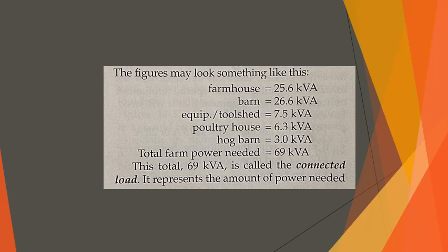In our example, 69 kVA times 0.35 equals 24.15 kVA, or 24,150 VA. At 240 volts, we arrive at 100 amps as our current needed for the farm.